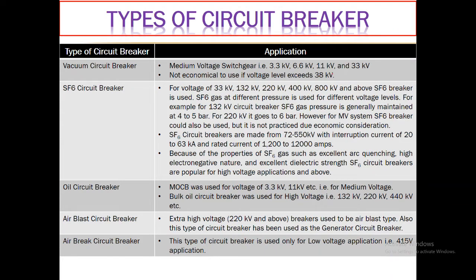Vacuum circuit breakers are normally applied for medium voltage switchgear, ranging from 3.3 kV to 33 kV. Above this voltage level, vacuum circuit breakers are not preferred. If asked how high a voltage vacuum circuit breakers can be used, the correct answer is 33 or 38 kV. Above that, they cannot be applied due to economical constraints. SF6 circuit breakers are used for voltages ranging from 33 kV to 800 kV and above.